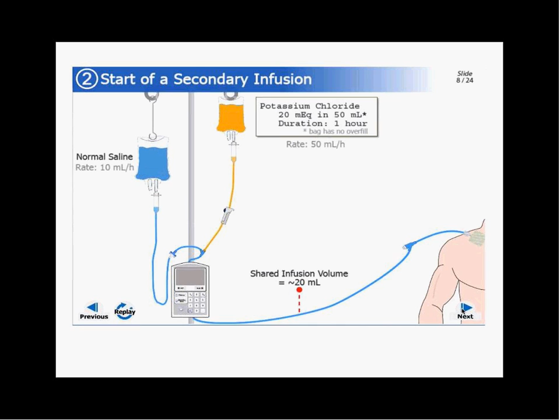Let's see. After the nurse hits start, the pump immediately switches from the primary to the secondary flow rate, but the infusion pump does not know what is infusing at the tip of the tubing. The shared infusion volume contains 20 milliliters of fluid. This is normal saline, not potassium chloride. After the first 20 milliliters of the programmed secondary infusion, the patient is actually receiving normal saline at a secondary flow rate of 50 milliliters per hour instead of 10 milliliters per hour.